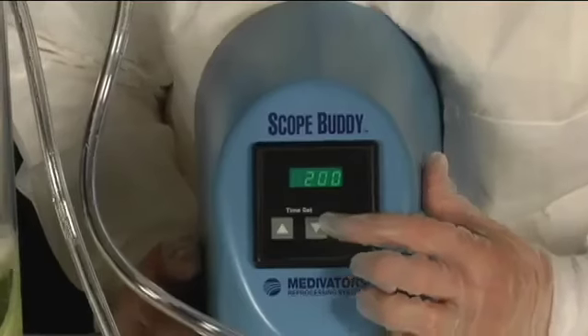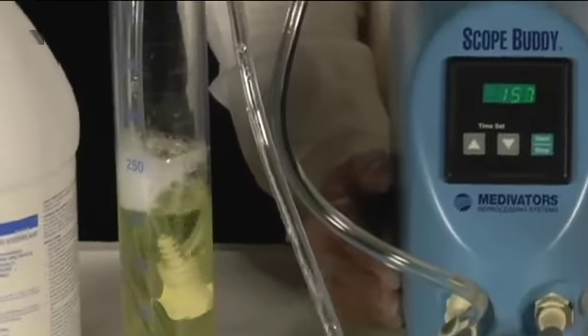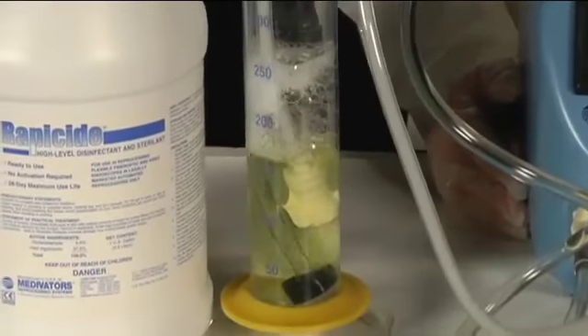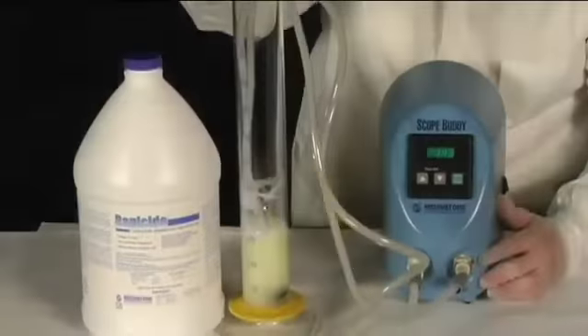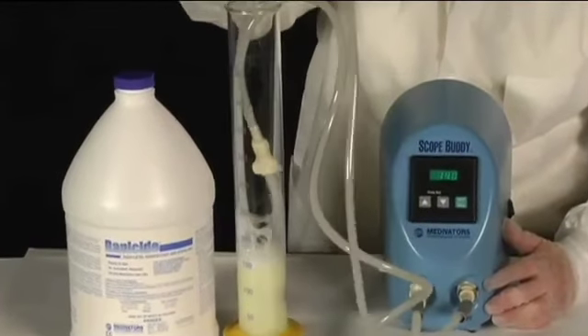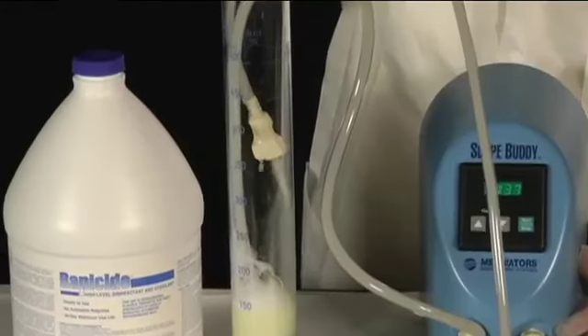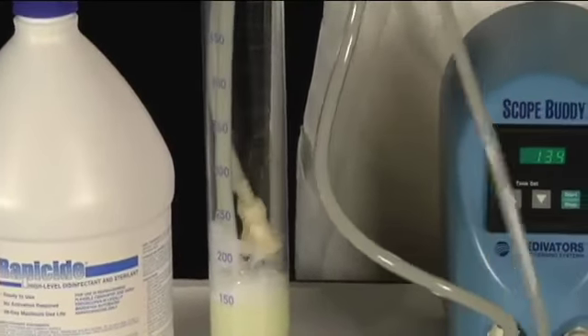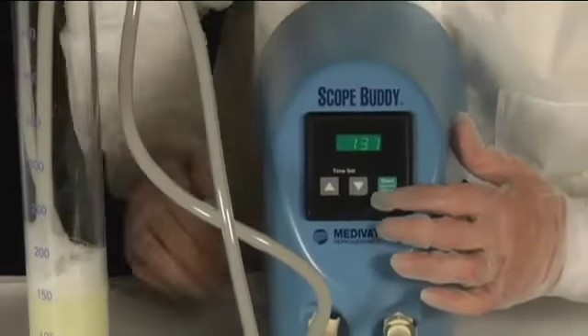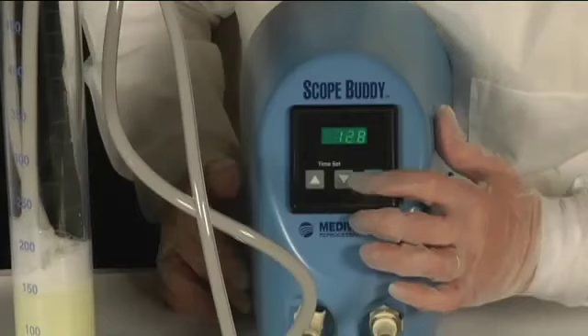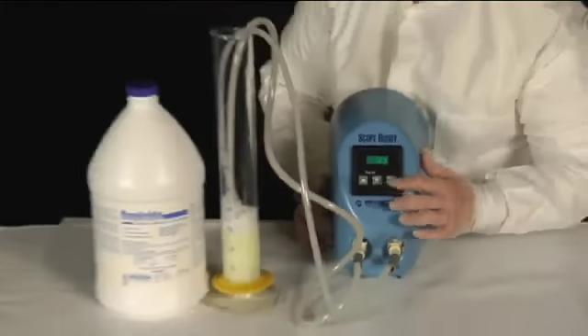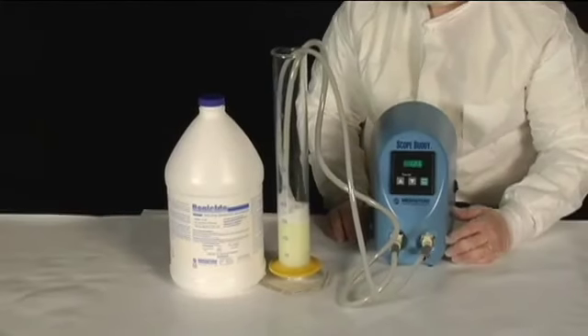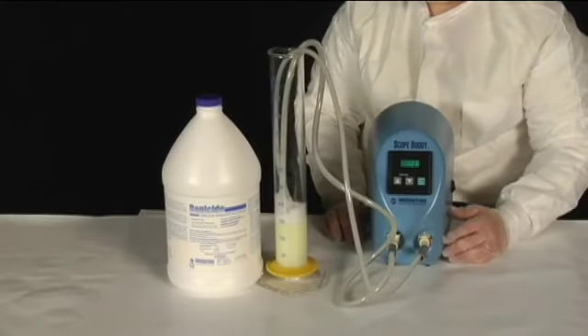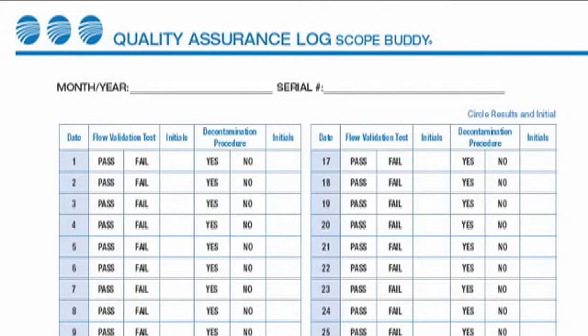Press the Start-Stop button to begin fluid delivery. Verify a steady column of solution is now exiting the outflow tubing. Press Start-Stop button to halt fluid flow. Referencing the decontamination manufacturer's labeling, allow the solution to remain within the device and all connection tubing until the specified decontamination time has elapsed. The system decontamination procedure is now complete and can be documented on the Scope Buddy Quality Assurance form.